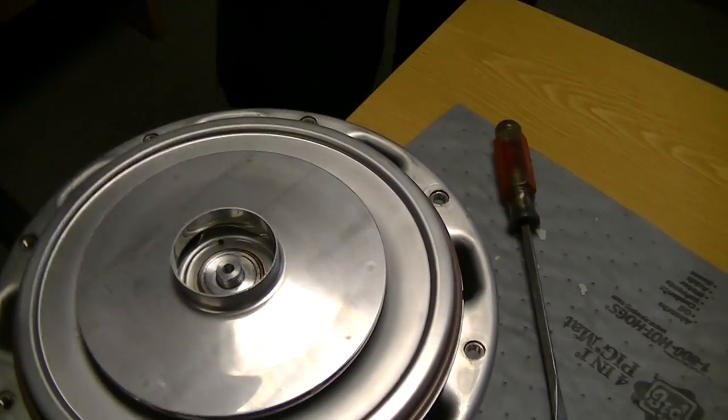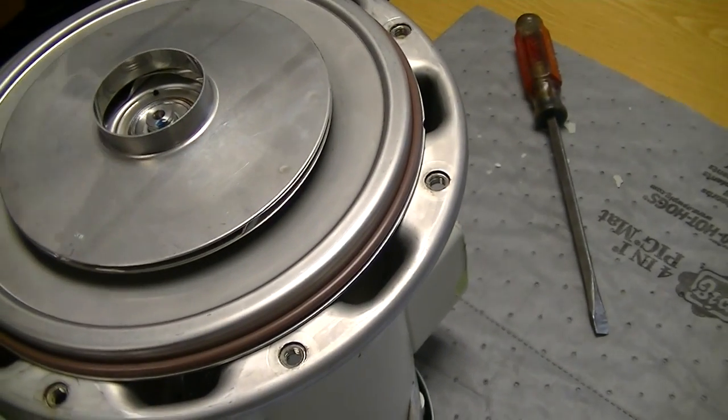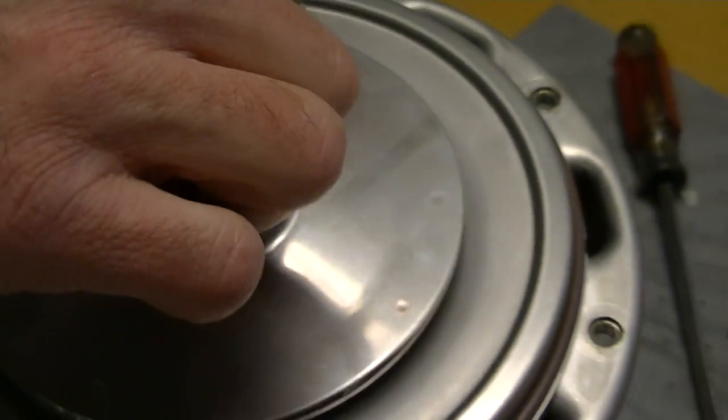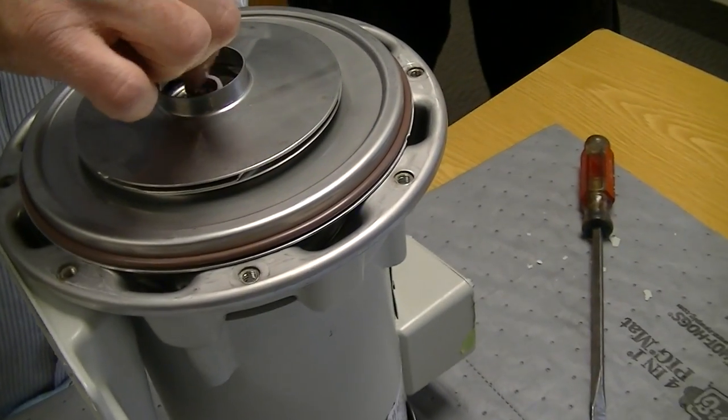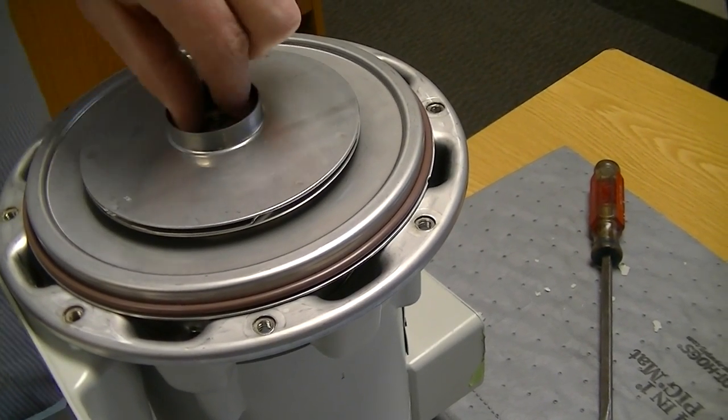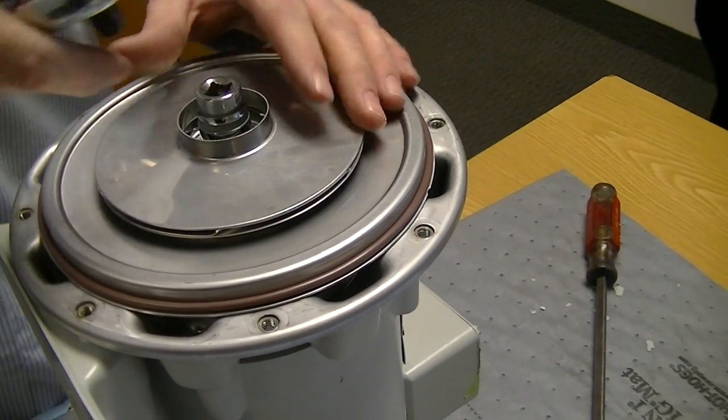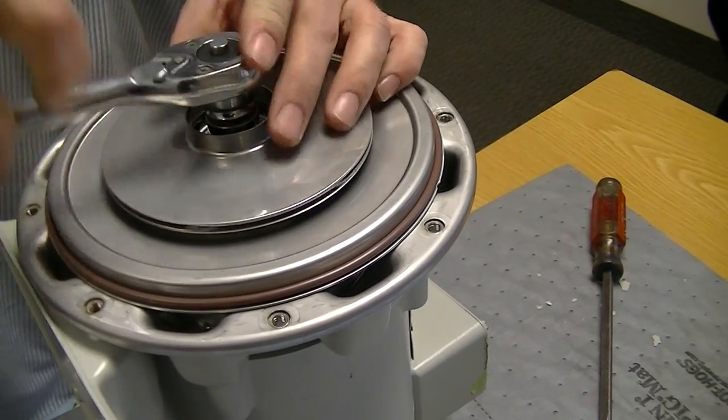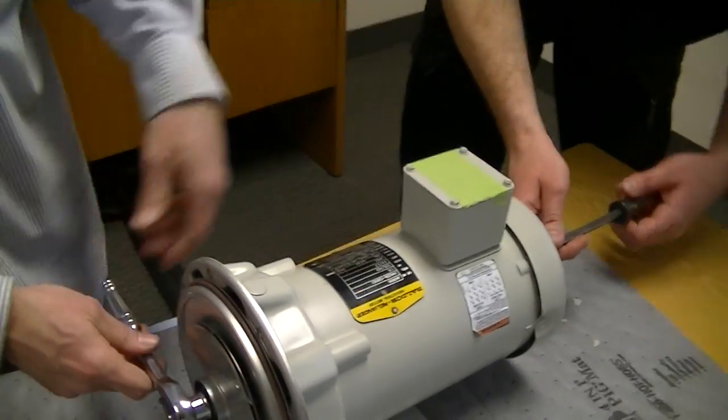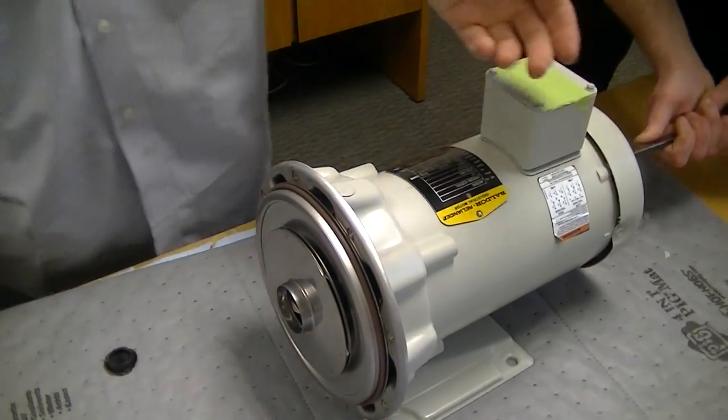Stand it back up. Put a little Loctite on there. Remember the blue one's what I always use, just a teeny little bit. You don't need a lot. It's not easy to get it apart if you put too much. And you just start your threads. This is where we're going to have to hold the back again to tighten this nut. Just hold this, a little crank, and that's that.